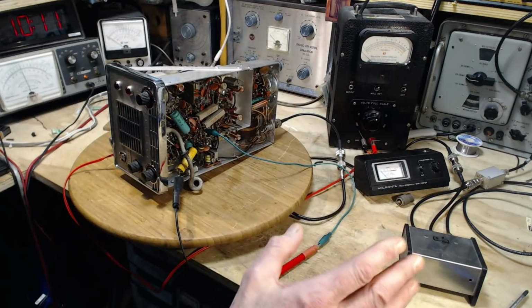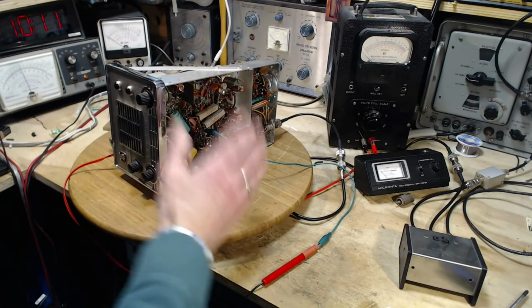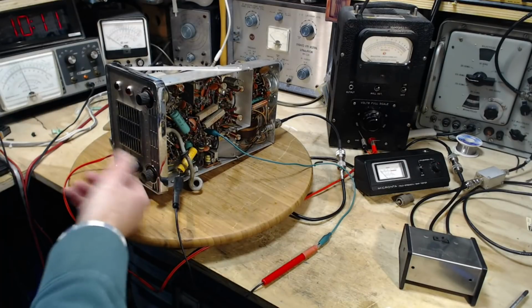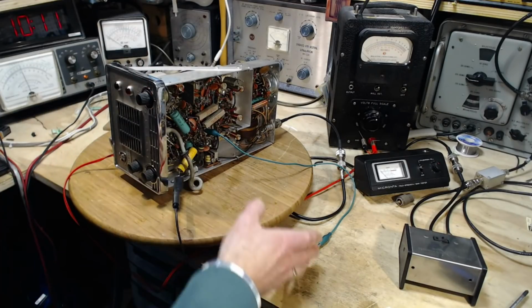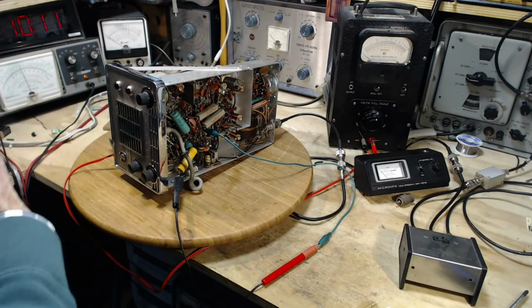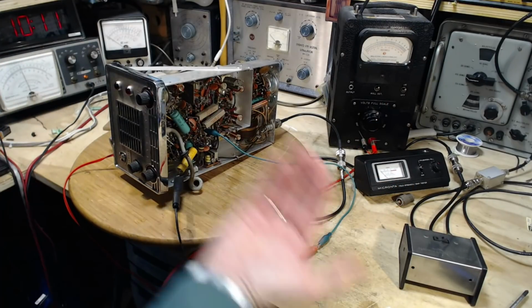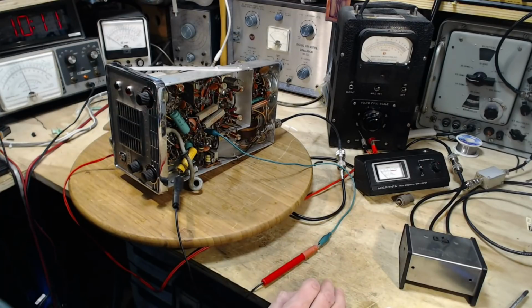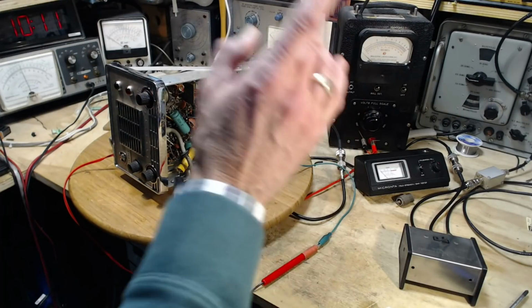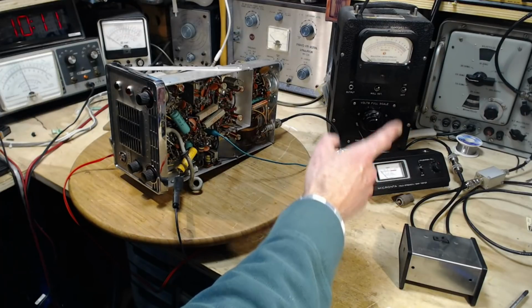So now the issue is, am I sending in a known signal level? Can I make a measurement of the AGC against this known signal level and look on the chart in the manual to see if it's correct or in the range it should be. So we'll start with, is there really a microvolt coming out of there?